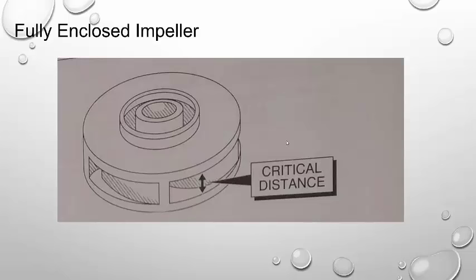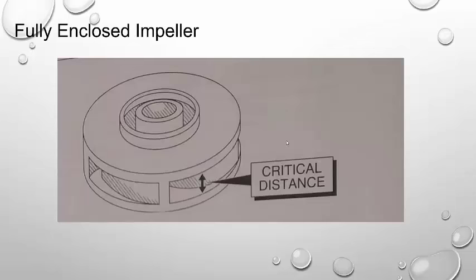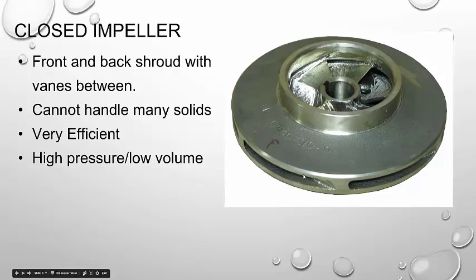So back to this critical distance. Here we're looking at the same fully enclosed impeller, your closed impeller. Critical distance here is across the spacing. So if I look back on this image, the critical spacing would be here, the distance between these two shrouds. And that's going to limit the size of solids. And these can be very, very small.